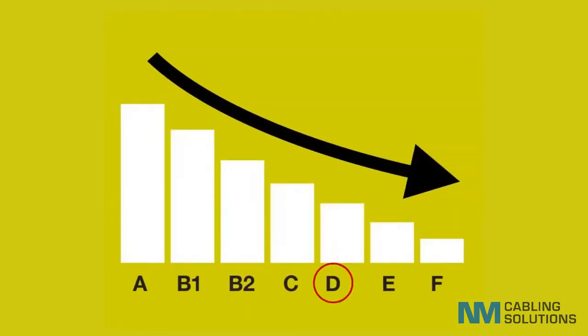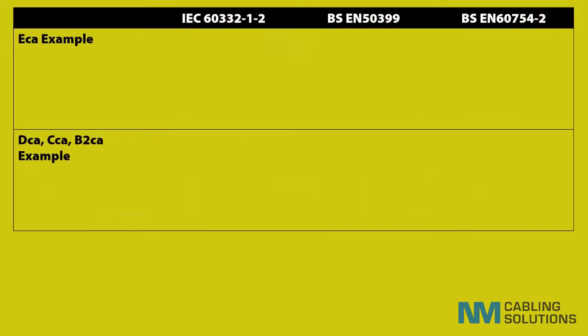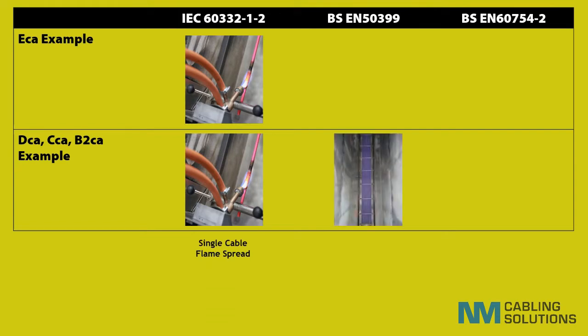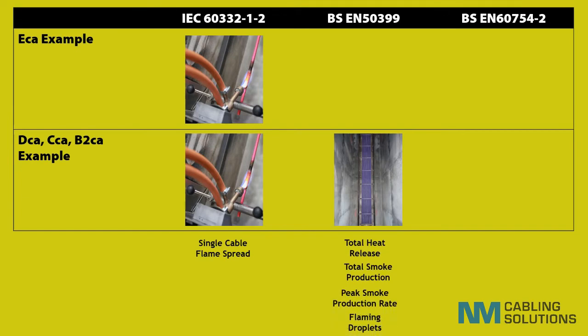For the DCA classification, we must also carry out the BS EN50399 and BS EN 60754-2 tests. These go much further than the previous bundled cable test employed for the non-discriminatory IEC 60332-3 series, which only ever had recommendations for flame spread limits and employed a 10 kilowatt flame. We now apply a 20.5 kilowatt flame to the test sample for a duration of 20 minutes, during which time we measure the following four parameters using BS EN50399: total heat release, total smoke production, peak smoke production rate, and flaming droplets.